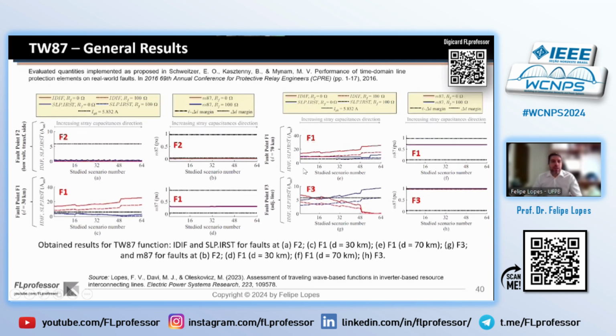For the differential element, the same. We can see that the fault location is not severely affected. We can see that some conditions here for external faults are properly respected, and the amplitudes of the travel waves guarantee the proper operation. But one of the conditions can present some instabilities here, like in faults F1 here and F3 here, because they cross between each other, demonstrating that the differential current can change its behavior in relation to the restraining current, depending on the values of the stray capacitances on the IBR side. And this is why some manufacturers are recommending to block these functions depending on the stray capacitances that are measured on the IBR side.